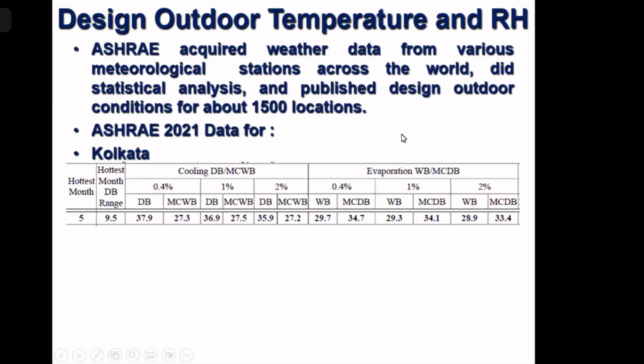So they found 36.9. And then they found that if we fix 36.9 degrees centigrade dry bulb temperature, when it actually occurred, what were the wet bulb temperatures during that time? So they took the mean of that wet bulb temperature. That is 27.5, the mean coincident wet bulb temperature. That means it is expected that the wet bulb temperature at 36.9 degrees centigrade dry bulb temperature will be around 27.5 degrees centigrade. So my outdoor design condition for Calcutta will be 36.9 degrees centigrade dry bulb temperature and 27.5 degrees centigrade wet bulb temperature.